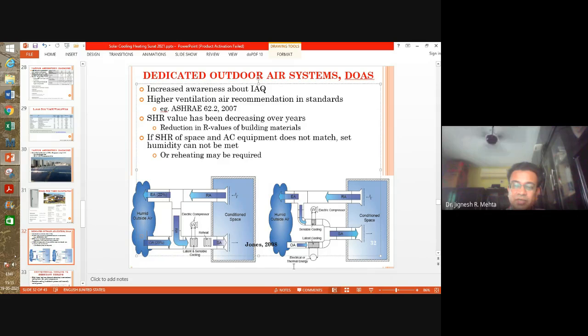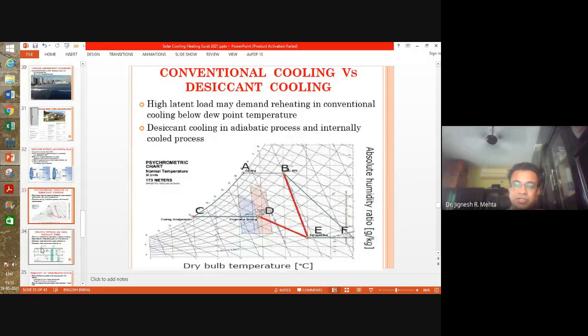So in such systems, the use of solar energy can become relevant with desiccant based air conditioning systems. This graph on the psychrometric chart shows you the processes possible in desiccant based air conditioning systems, mainly dehumidification, the removal of moisture. In conventional systems, you will cool the air below its dew point temperature, and if this temperature is too low, you may have to reheat and then put it in the conditioned space. With a desiccant cooling system, if it is an adiabatic system, you are not removing heat simultaneously, so it will move along this line. That is, there will be a rapid rise of temperature along with a reduction in humidity ratio.